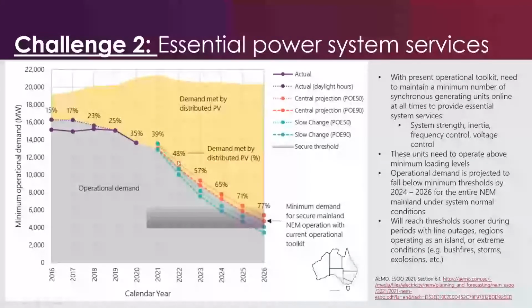There's certainly things that we can do to address this. The first of those is to investigate how to address this in various planning processes. So there are definitely ways you can drop this line down by getting those services from other places. So we can use synchronous condensers, for example, to provide system strength and inertia. We've recently, or ElectraNet has recently, commissioned synchronous condensers in South Australia, which are providing a lot of those services now. Large batteries are also very capable providers of frequency control, and all of those will drop this line down so that we can operate with lower levels of operational demand.